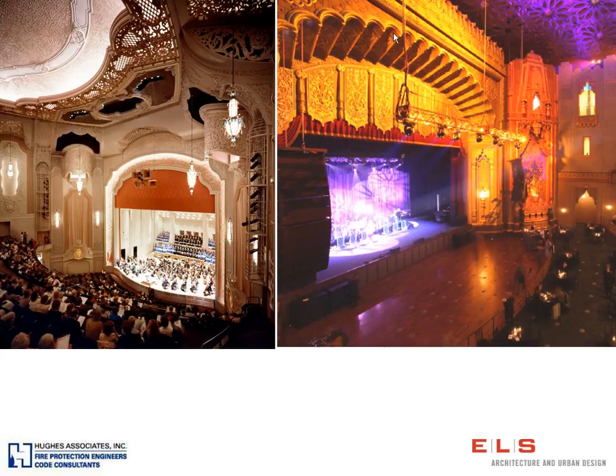But another situation also occurs, and that is if it stays hot enough, if you have a fast-growing big fire, and it reaches your ceiling, and it does activate the sprinklers, with all of that plume of fire that's very hot, you are going to have evaporation of your water particles before it can ever get to the ground and actually get to the seat of your fire. So in very tall spaces, the sprinkler system may not be effective. So there may be room for either omission or an alternative method to address that particular space and then still take advantage of some of the benefits that are allowed by the California Historical Building Code.